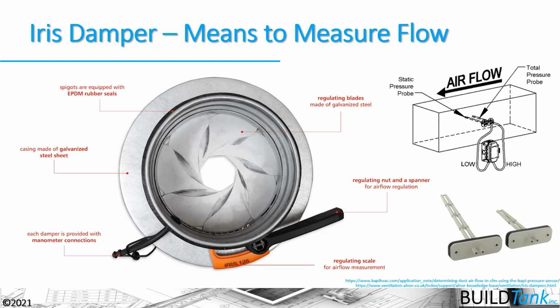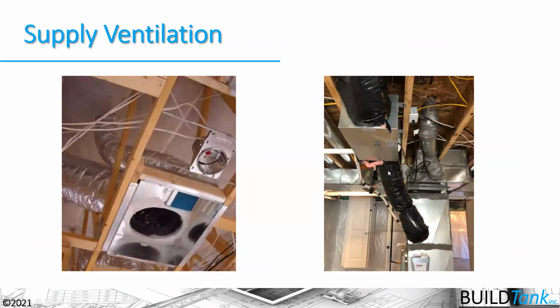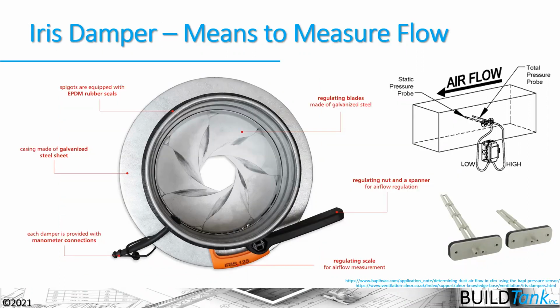So if you're using supply side ventilation, you want to specify a damper that has a port where you can measure the flow across the damper and set that flow rate specifically, because otherwise it's really dependent on how close this duct is coming into the return side, how close that is to the furnace fan. That will determine the flow of air through that duct. I can measure that flow with these flow measuring devices on the right side here, but I can't adjust the flow rate like I can with an iris damper.